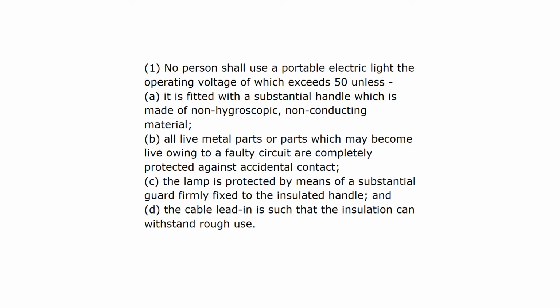Portable electric lights. No person shall use a portable electric light the operating voltage of which exceeds 50 unless it is fitted with a substantial handle which is made of non-hygroscopic, non-conducting material, all live metal parts, or parts which may become live owing to a faulty circuit, are completely protected against accidental contact. The lamp is protected by means of a substantial guard firmly fixed to the insulated handle, and the cable lead-in is such that the insulation can withstand rough use.